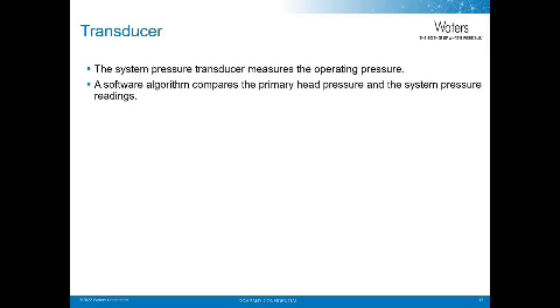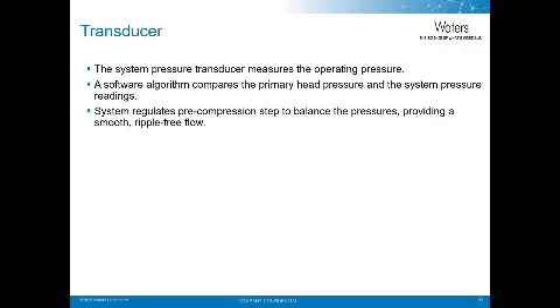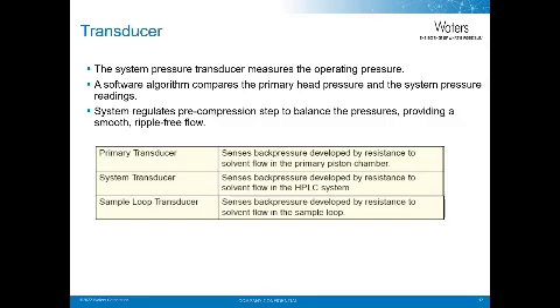Now let's talk a little bit more about transducers. Transducers are used throughout the instrument to measure the pressure of the system. The system pressure transducer measures the operating pressure. A software algorithm then compares the primary pump head pressure and the system pressure readings. The system then regulates the pre-compression step to balance the pressures, providing a smooth, ripple-free flow. The primary transducer senses back pressure developed by resistance to the solvent flow in the primary piston chamber.